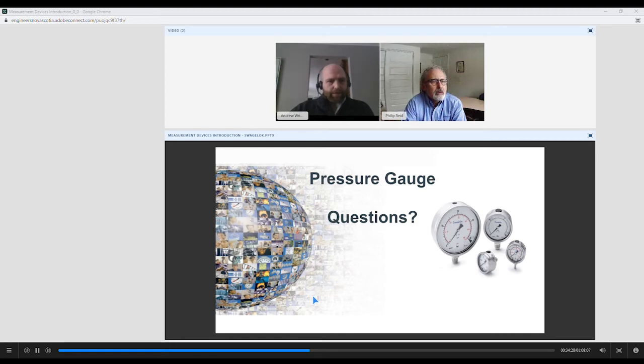If you can't calibrate the gauge, would you have to replace them after a specific time? Is there a standard age depending on the type? And this is from Martha. So often, Martha, it comes down to code requirements or the application that it's put into or specifications around the project. I've seen commonly that gauges should be recalibrated on an annual basis. But I've also seen applications where calibration isn't required at all. So it comes down to the application that you're working on, and if you do a little bit more digging into that, you should be able to find some answers. But general rule of thumb, if calibration is required, they should be recalibrated on an annual basis.